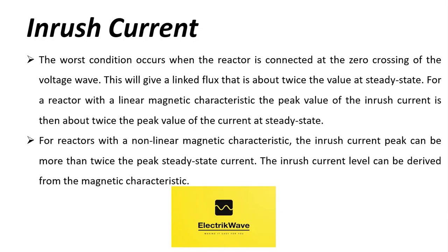The worst condition occurs when the reactor is connected at the zero crossing of the voltage wave. This will give a linked flux that is about twice the value at steady state. For a reactor with a linear magnetic characteristic, the peak value of the inrush current is then about twice the peak value of the current at steady state. For reactors with a non-linear magnetic characteristic, the inrush current peak can be more than twice the peak steady state current. The inrush current level can be derived from the magnetic characteristic.